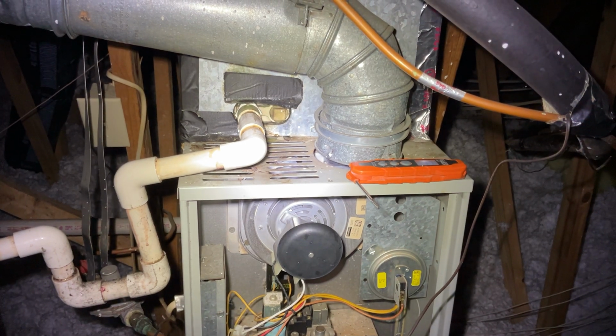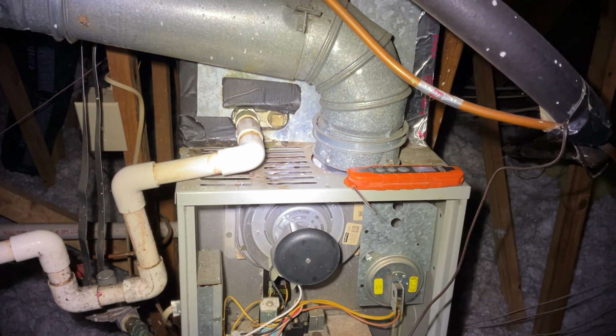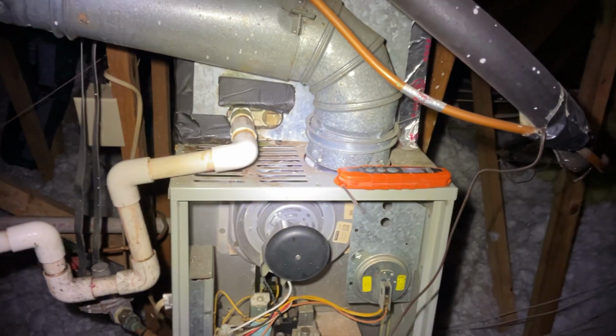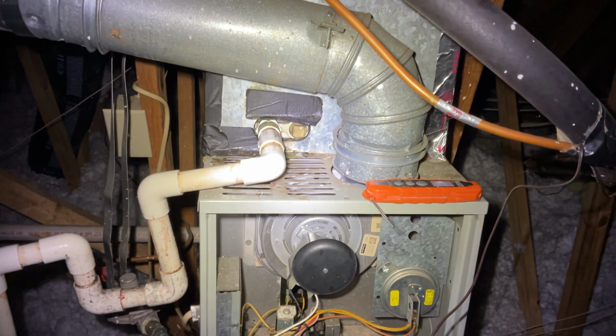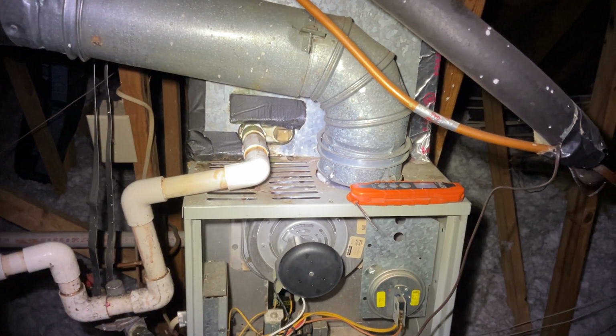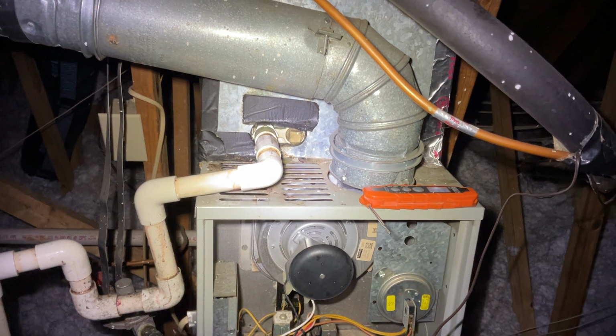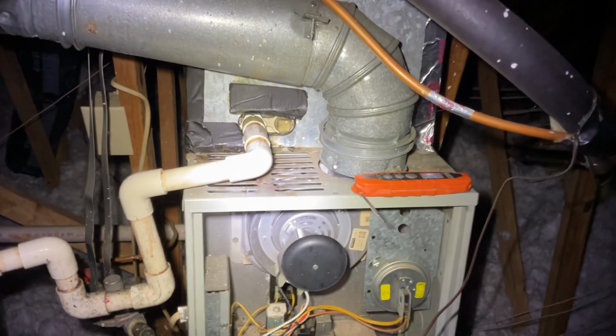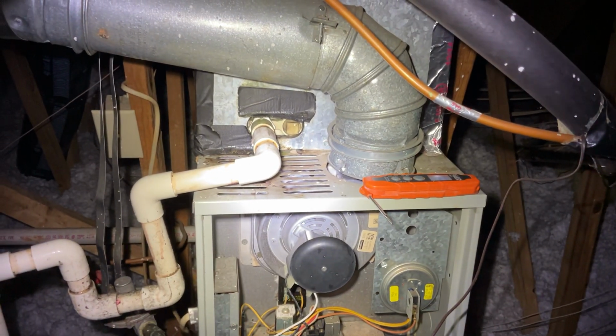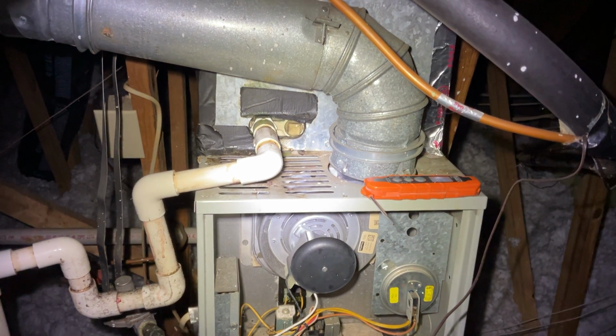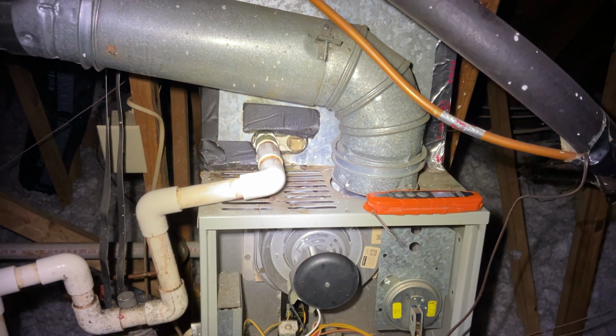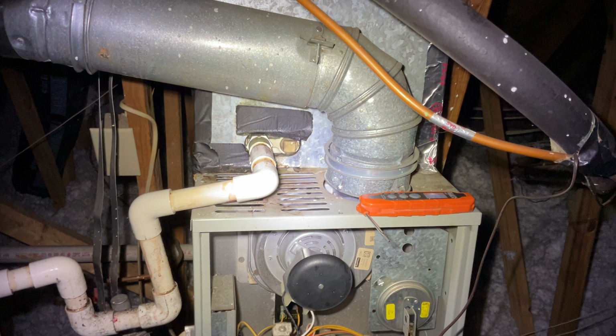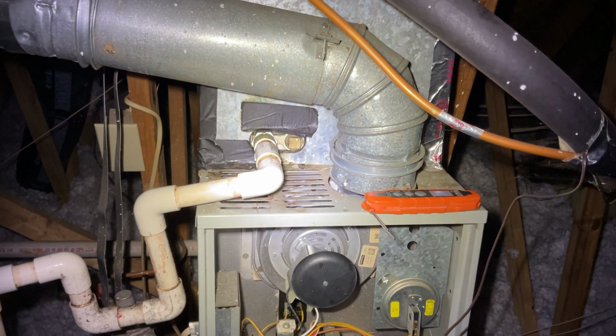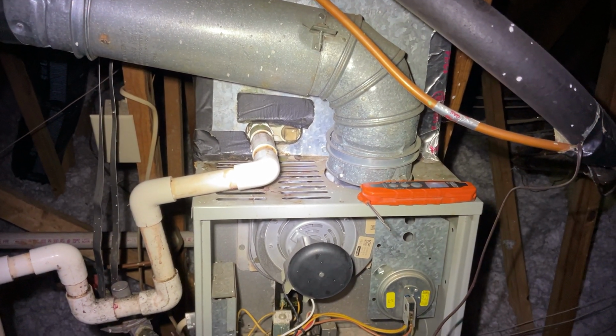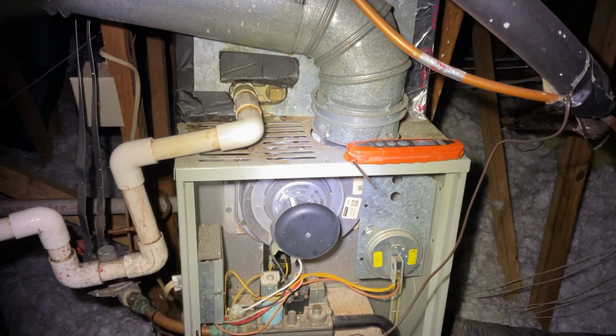There are acceptable limits. There's a lot of variables that can affect your range there and that temperature drop, but you want to be somewhere between, ideally, the 15 to 20, maybe 22 degree mark. Here we have an older system. The air filter is dirty, so I was expecting, actually I don't know what I was expecting. Old units don't typically have good differentials, and this one didn't.